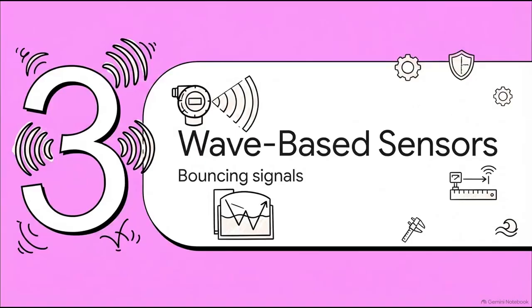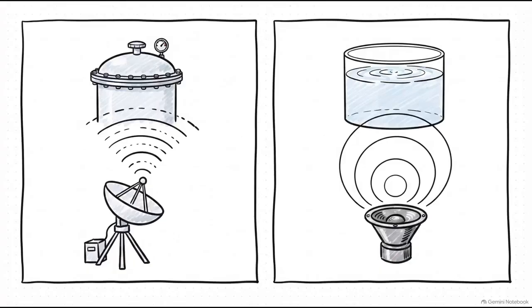Let's keep moving. Section 3, wave-based measurement sensors, bouncing signals to calculate distance. So now we're looking at non-contact methods, and it usually comes down to 2 heavy hitters, radar versus ultrasonic. Radar transmitters fire microwave signals down at the material and time the echo. The great thing about microwaves is that they don't care at all about air density, color, or pressure changes inside a closed tank, making them perfect for extreme chemical setups.